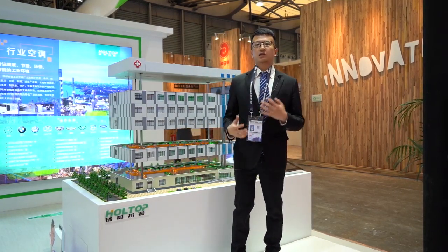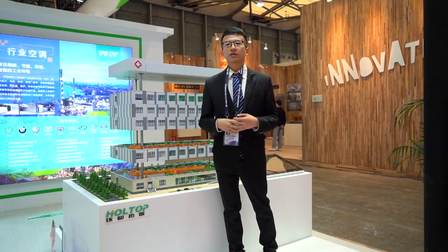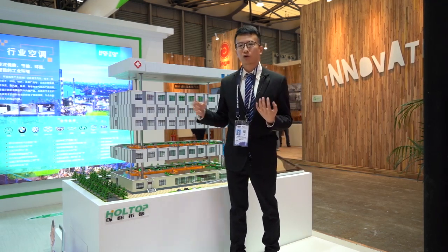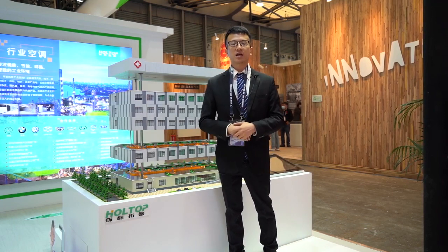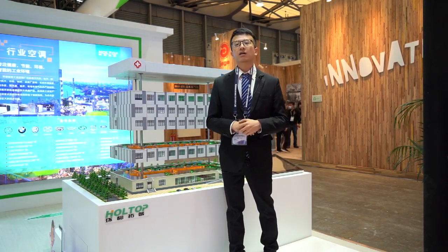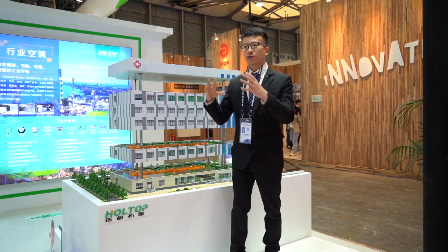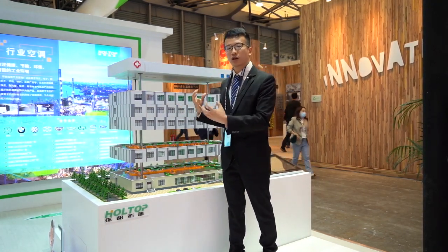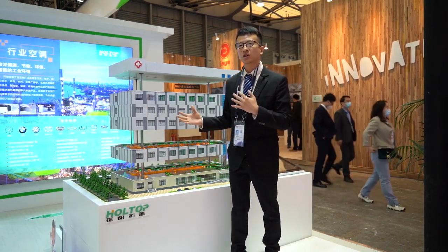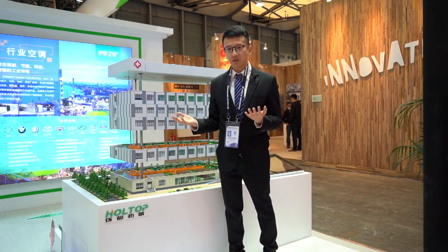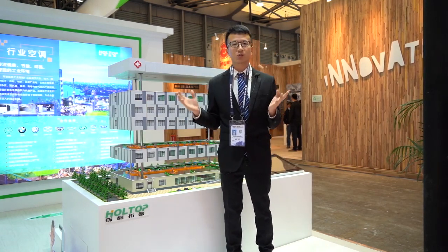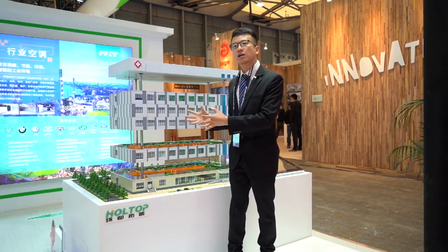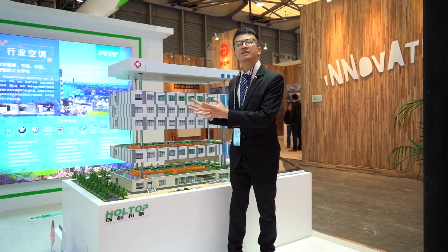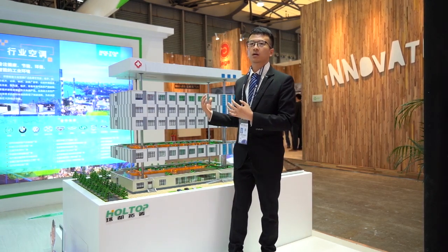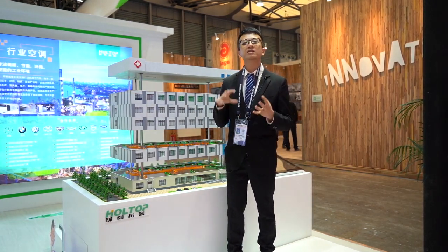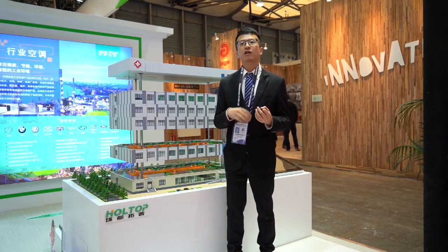In the design of a smart control intelligent fresh air system, there are some things we should think about for different projects, and usually there are 4 aspects. The first one is the airflow route, which means how the AHU extracts the fresh air from outside and sends it to each room, and what the steps are. The major principle is to send the fresh air to the clean area first, then to the semi-contaminated area, and last to the fully contaminated area.